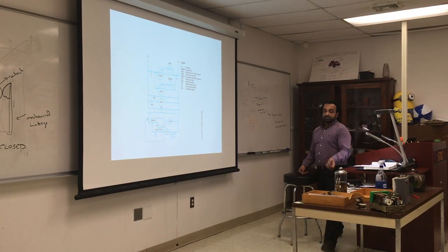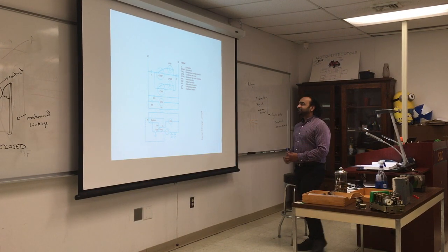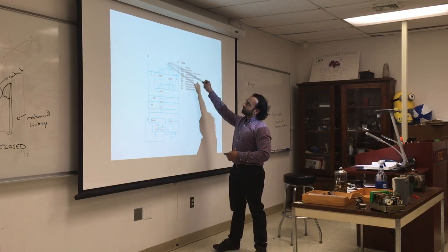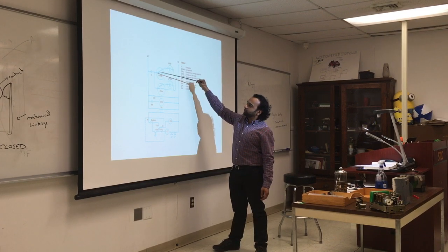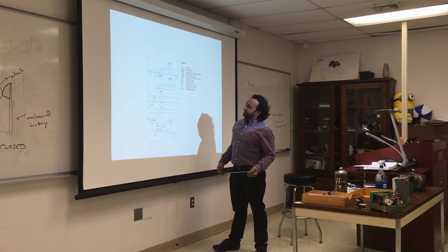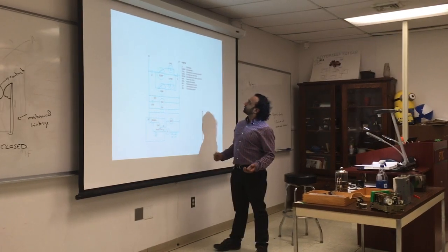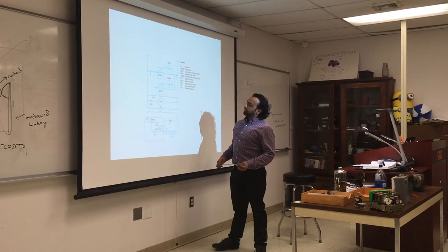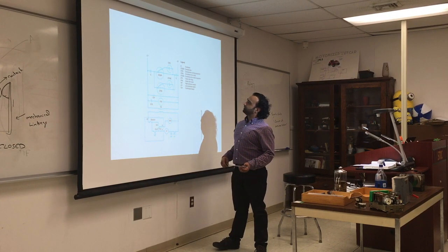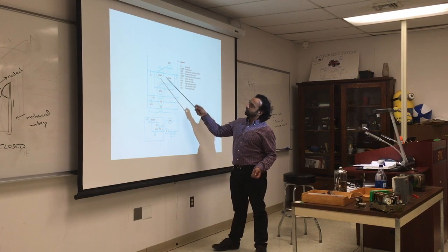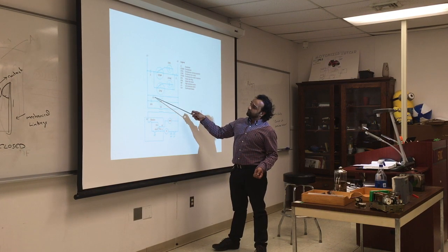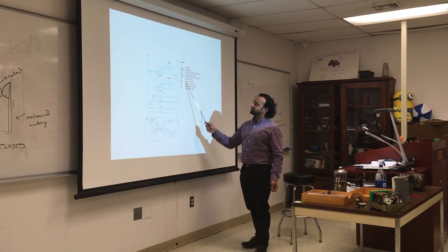Alright. Another schematic here. This is also called a ladder diagram because it looks like a ladder. We have L1 and L2 with components connected to it. I highly doubt you'll see something like that for installation, but this tells you how the equipment is actually wired. This is the whole control for an air conditioning unit or a fridge. These are the contactors with the relays, compressor, fan motor connected in parallel, crankcase heater. Again, look at the legend, it tells you what everything is.